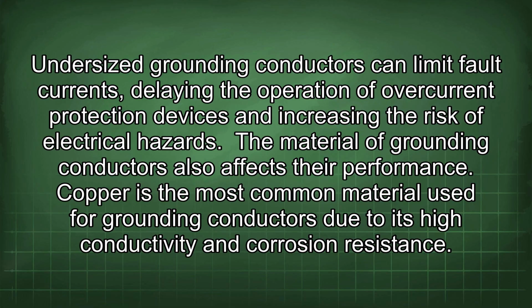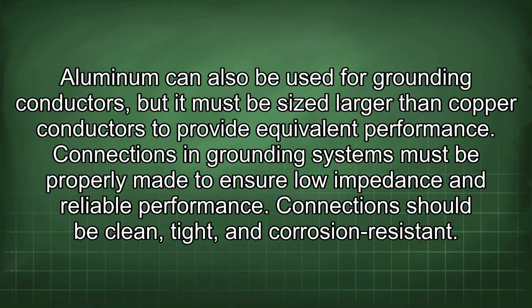Copper is the most common material used for grounding conductors due to its high conductivity and corrosion resistance. Aluminum can also be used for grounding conductors, but it must be sized larger than copper conductors to provide equivalent performance. Connections in grounding systems must be properly made to ensure lower impedance and reliable performance.